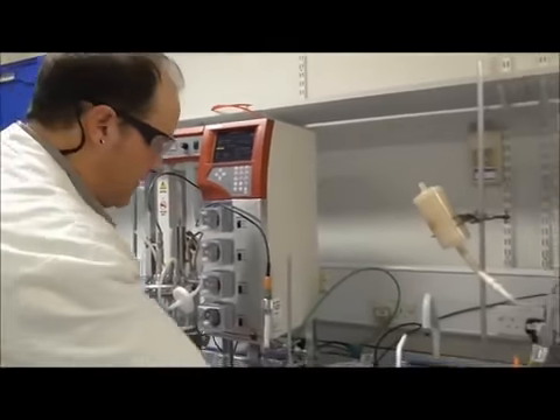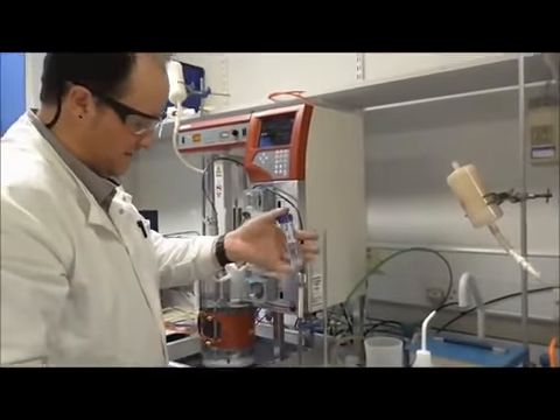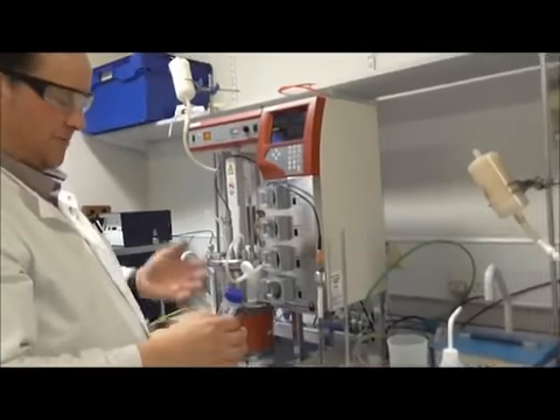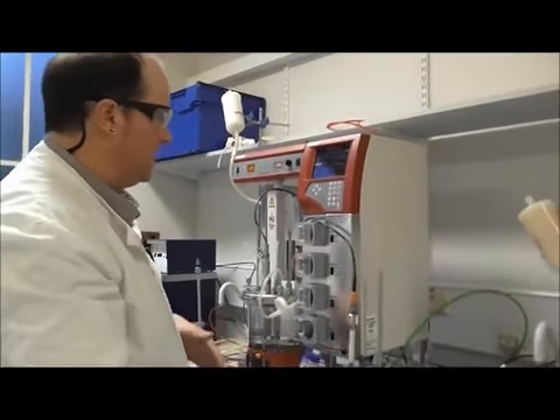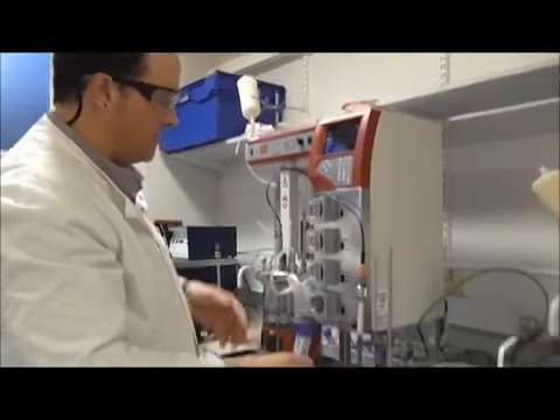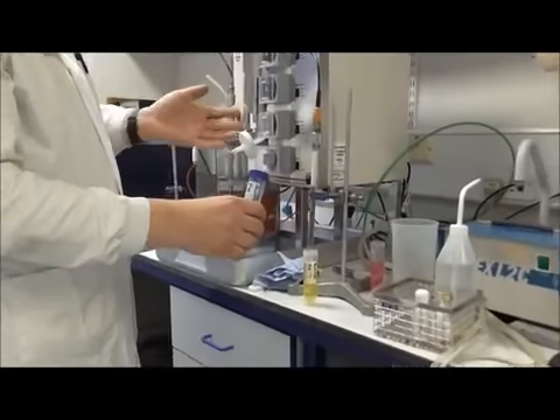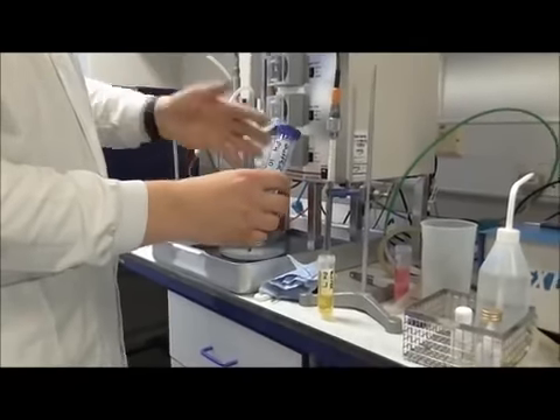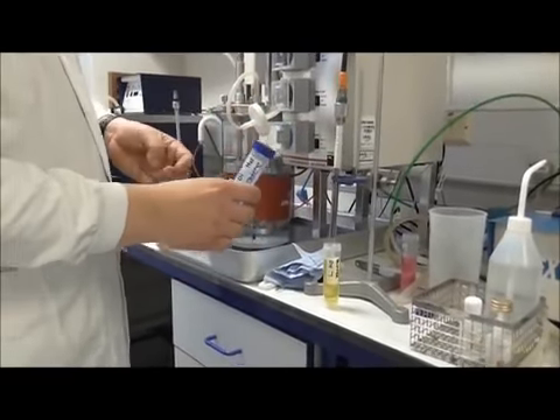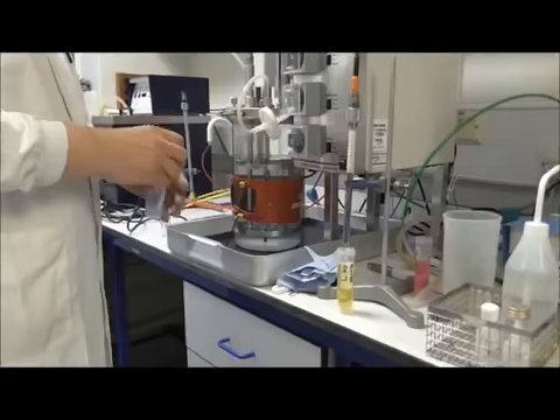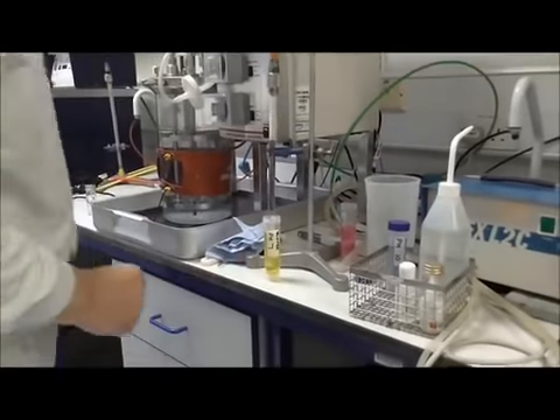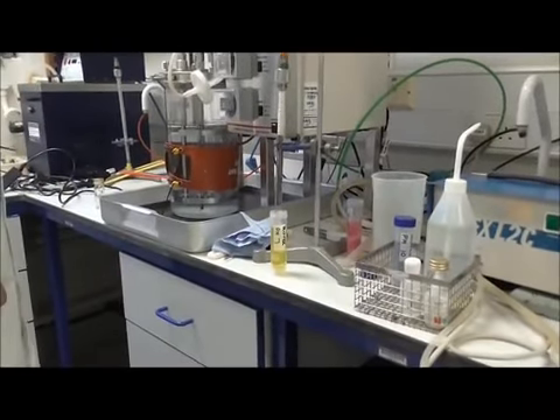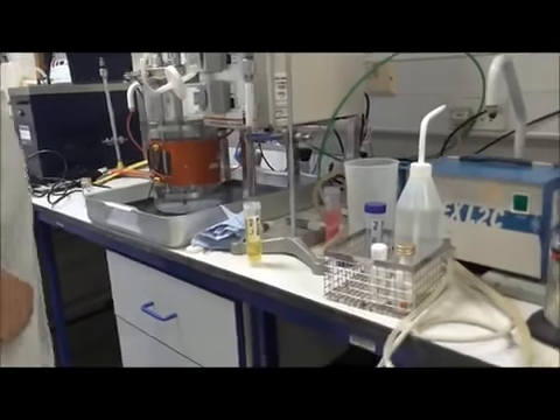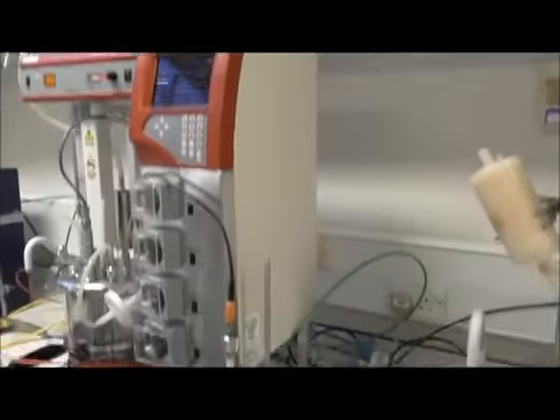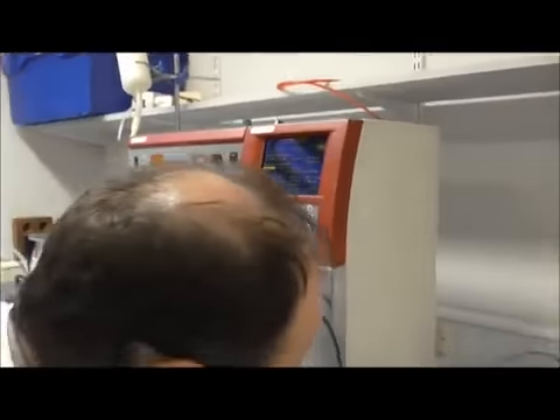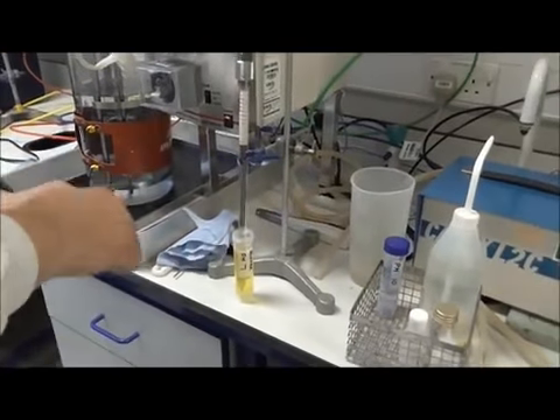Carrying on. We have a third buffer, number 10, the blue stuff. Sometimes to check a probe's performance, we'll pop it in number 10 and we'll see how far up the scale it will go. If the probe indicates about 9.5, 9.6, because this stuff does deteriorate, we won't get it 10 exactly, it says the probe is in sort of fine fettle. But we won't do that today. Oh, it is all over the place. Right, never mind, we'll leave that for a little bit. Oh, I'll pop the cap back on number 4.